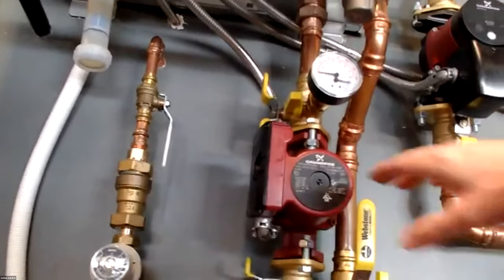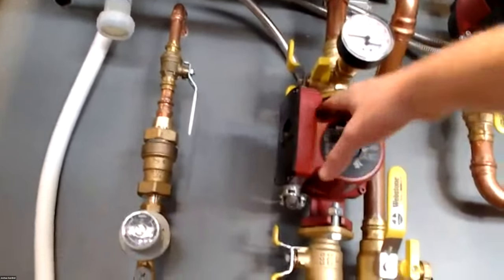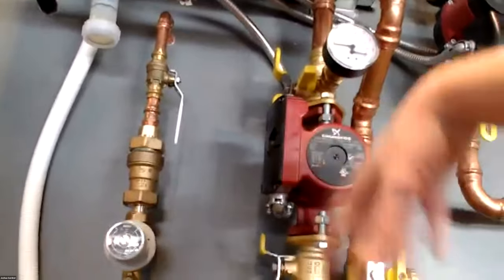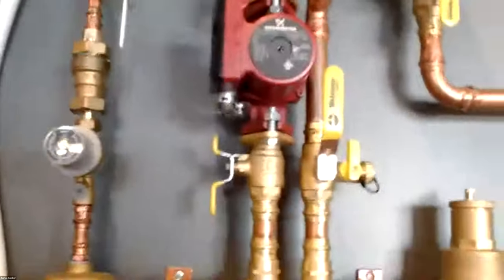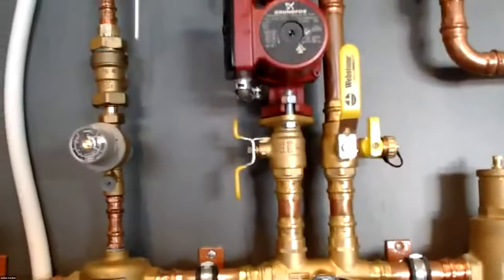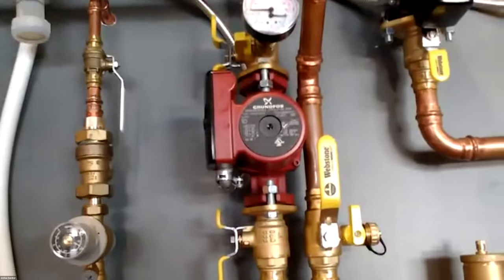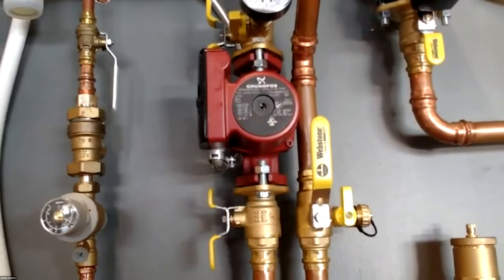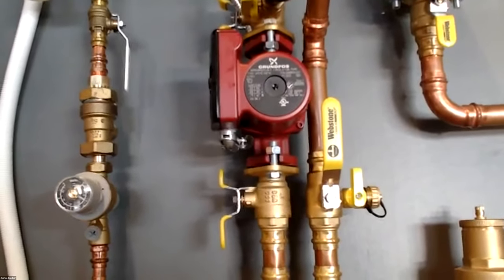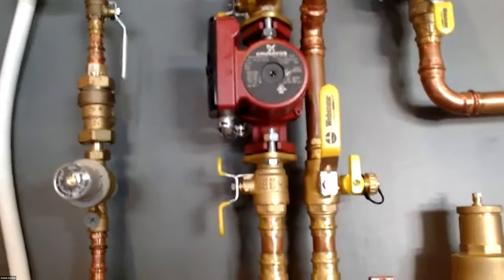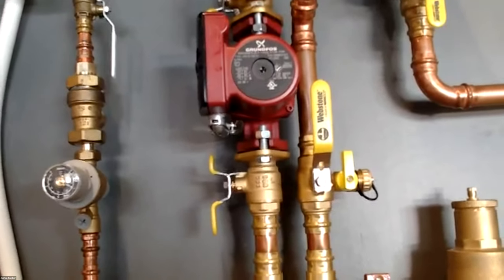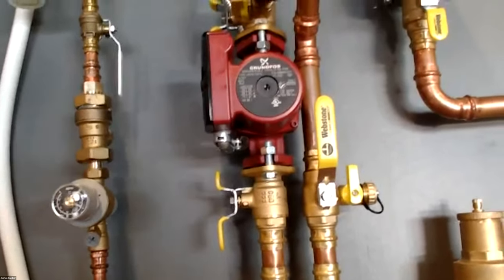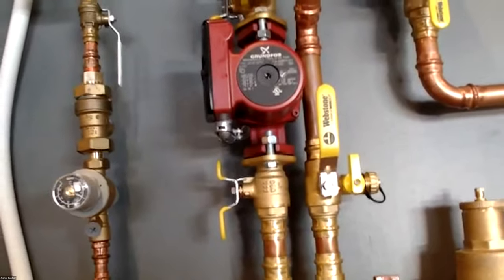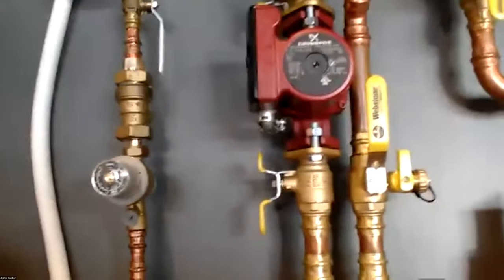But again, for these heating only boilers, the next version will have the system pump installed, so you won't need to worry about that anymore. But for right now, the heating only boilers, if you're going to use them, just keep in mind those are our pump recommendations. And also, if you're going to be doing an indirect, match your indirect pump with your boiler pump if you're doing it on the primary side. If you're doing it indirect on the secondary side, use whatever pump you want, doesn't matter. But we want adequate flow on the indirect.